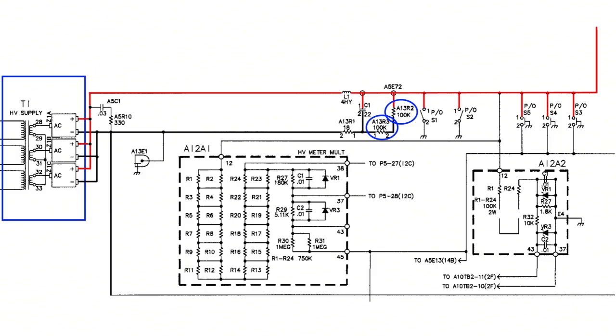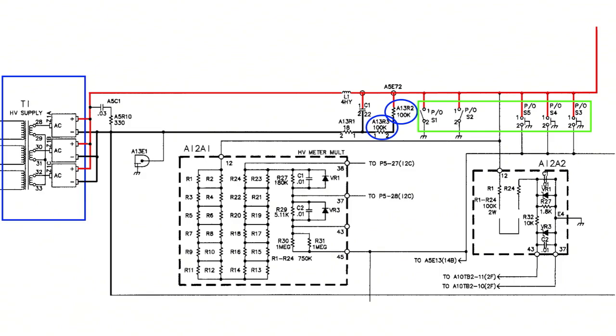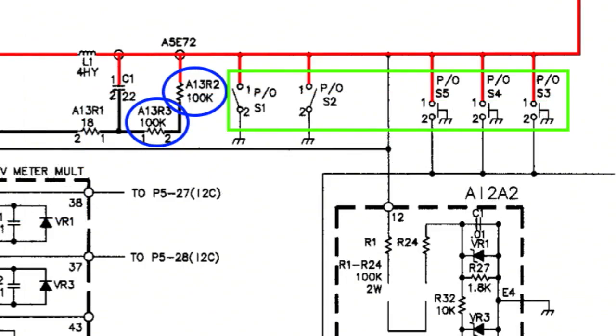In the next photo, if you'll remember I mentioned a minute ago about the interlocks, inside that green rectangle there, there's a lot of switches that are tied to ground. Some of them are tied directly to ground. Some of them are drawn similar to a push button. There we go. And they're also tying the screen supply to ground. What those are is every door on that transmitter has one of these interlock switches. When you take that door off or open it, that switch is supposed to immediately short out that high voltage to ground to prevent you from accidentally getting across it.